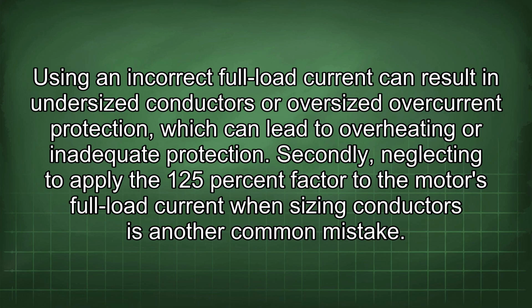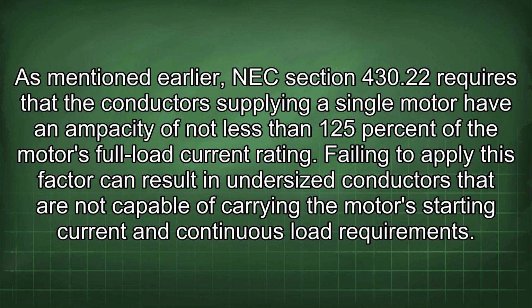Secondly, neglecting to apply the 125% factor to the motor's full load current when sizing conductors is another common mistake. As mentioned earlier, NEC Section 430.22 requires that the conductors supplying a single motor have an ampacity of not less than 125% of the motor's full load current rating. Failing to apply this factor can result in undersized conductors that are not capable of carrying the motor's starting current and continuous load requirements.